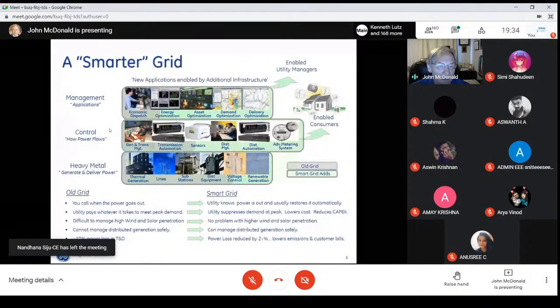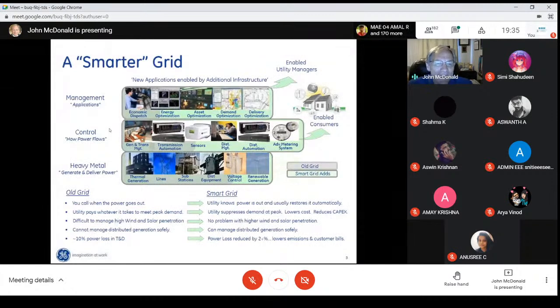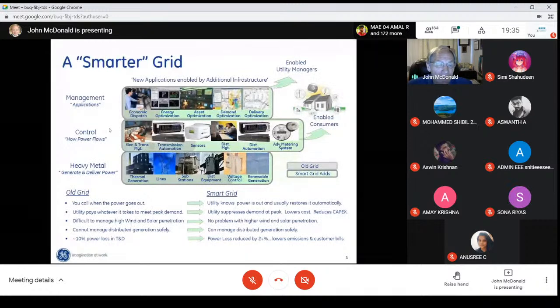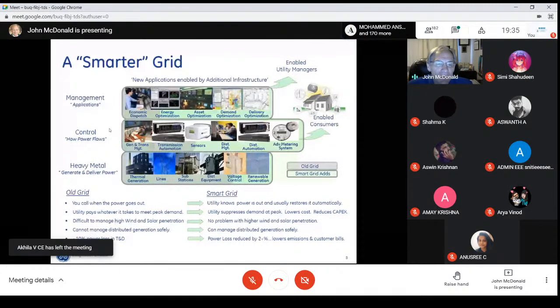Very important. We used to, for many years, wait until something failed, and then we reacted. That's kind of silly, right? Kind of stupid to do it that way, because you've lost equipment. It's been destroyed. It's failed. And many times, a transformer in a substation would have what we call a catastrophic failure, and it would damage all the equipment in the substation with an explosion, with a fire, right? Why wait until something failed? Why not get health information on the asset, use analytics to predict the health of the asset and prevent a failure from occurring? That makes more sense, right? So that's what we're doing today. That's called predictive. And we use specialized sensors to give us that information.